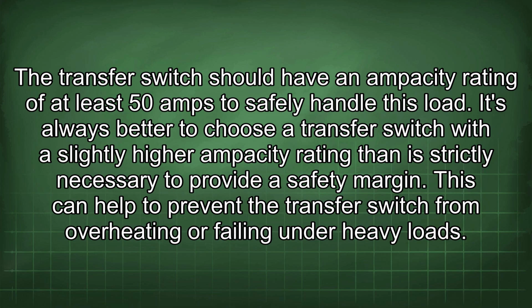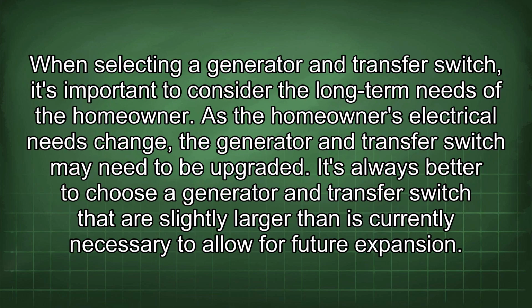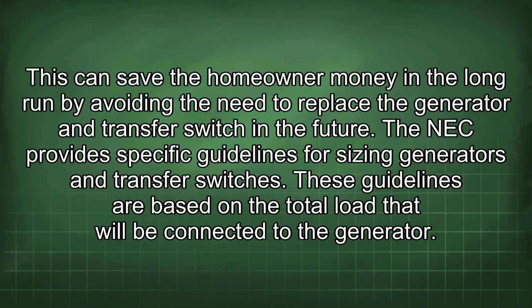It's always better to choose a transfer switch with a slightly higher ampacity rating than is strictly necessary to provide a safety margin. This can help to prevent the transfer switch from overheating or failing under heavy loads. When selecting a generator and transfer switch, it's important to consider the long-term needs of the homeowner. As the homeowner's electrical needs change, the generator and transfer switch may need to be upgraded. It's always better to choose a generator and transfer switch that are slightly larger than is currently necessary to allow for future expansion. This can save the homeowner money in the long run by avoiding the need to replace the generator and transfer switch in the future.